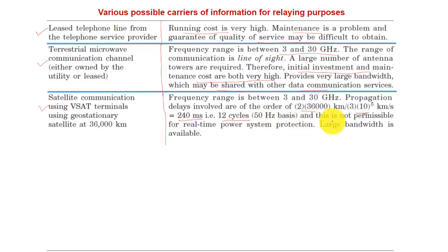This is therefore not permissible because the propagation time is very large. We need a carrier channel which can transmit the signal in much less than 20 milliseconds.